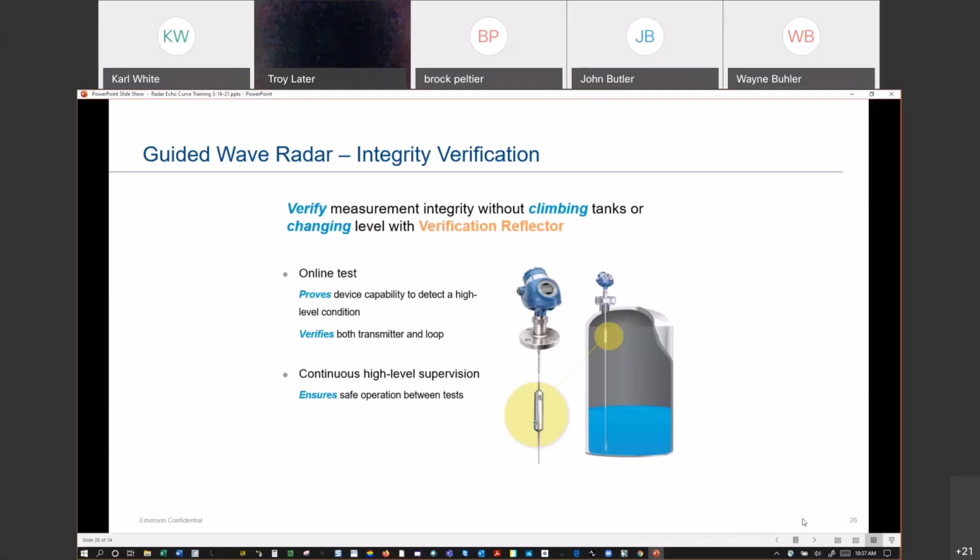If you look at the echo curve, the reflection you get off of this, it's pretty small. It wouldn't be anything like a peak off of the oil surface or anything. It's just a really small, kind of like a reference reflector on a DVC probe. Okay.